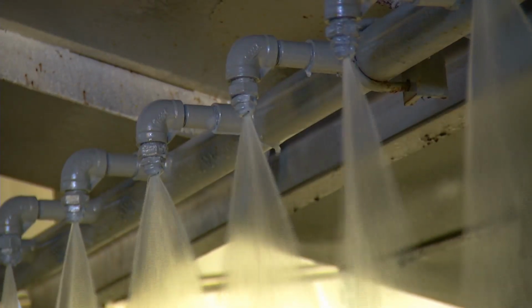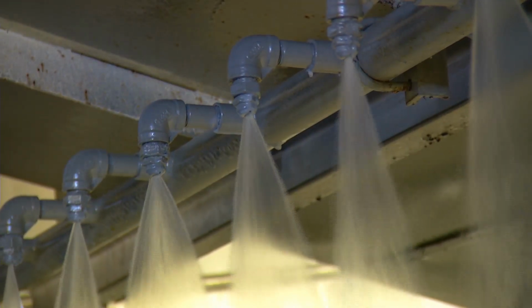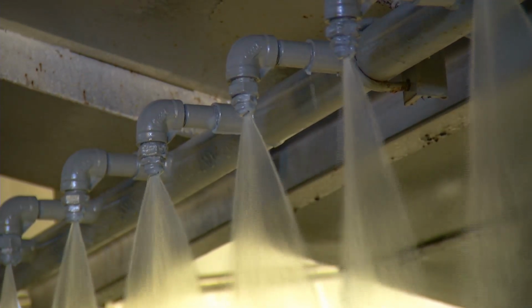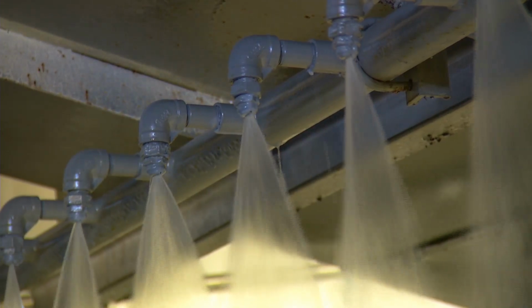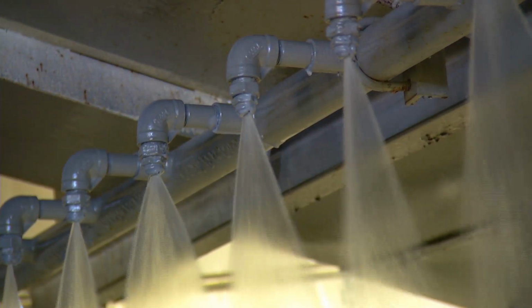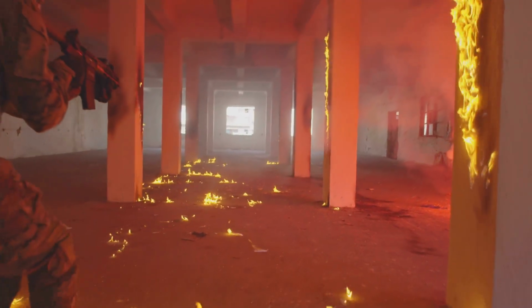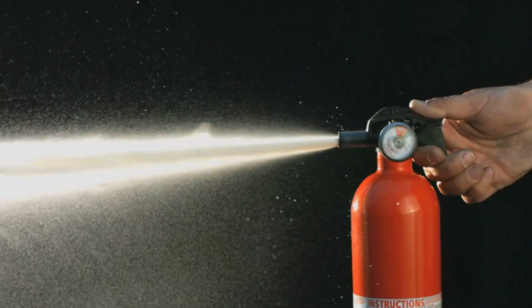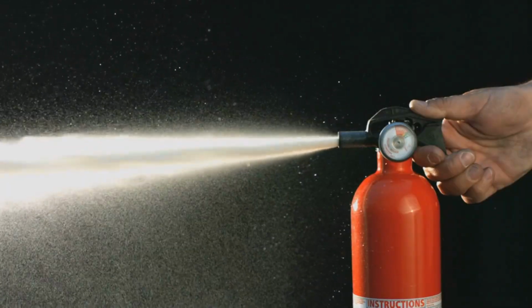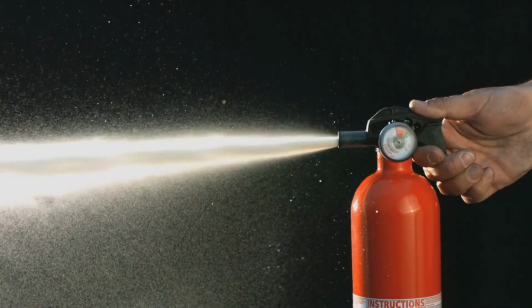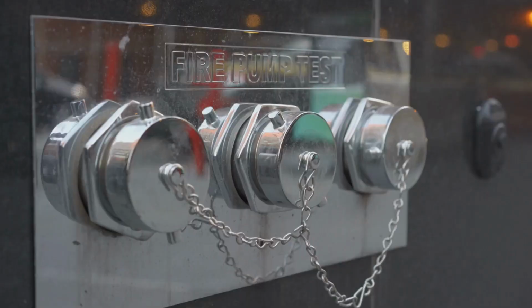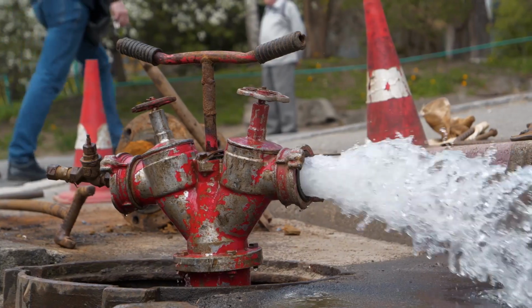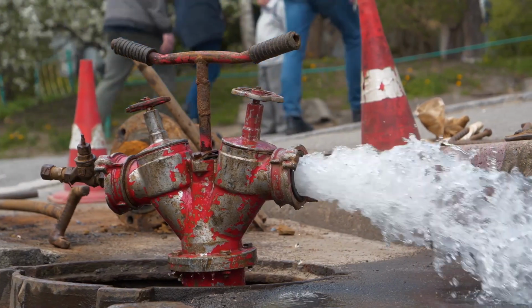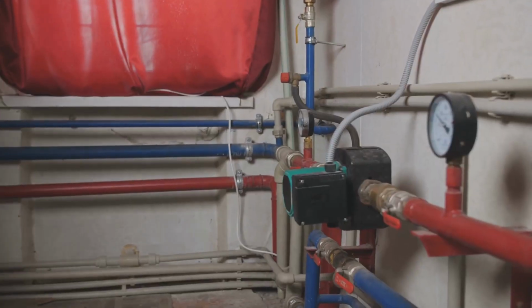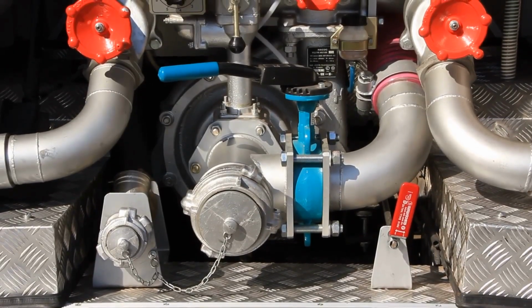Then there are deluge systems used in high-risk environments like chemical plants. In those systems, all sprinkler heads are open, and water is released across the entire area when triggered. But for most buildings, it comes back to the same idea: individual sprinkler heads responding to heat. Now let's talk about where the water actually comes from. Because spraying water is only useful if there's enough of it and enough pressure. In many buildings, sprinkler systems are connected directly to the city water supply. But that's not always enough. Large buildings often need additional support.